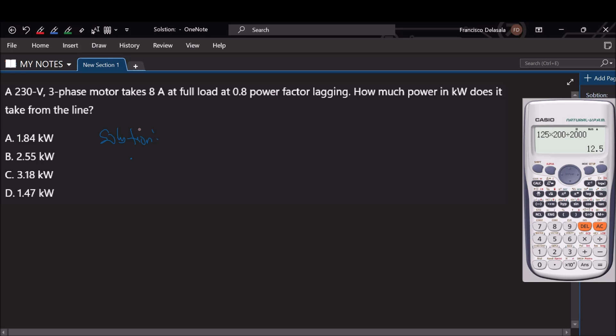Next question. A three-phase 230-volt motor takes 8 amperes at full load at 0.8 power factor lagging. How much power does it take from the line? Solution: power in an AC circuit, for three-phase, is equal to square root of 3 times the voltage times the current times the power factor.